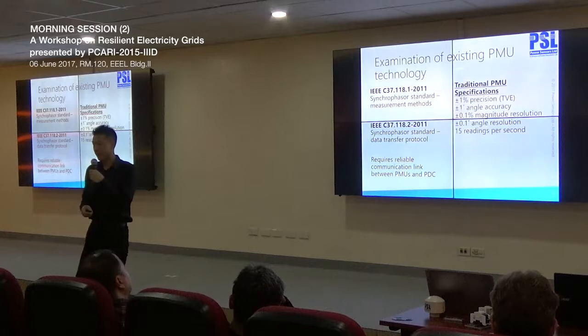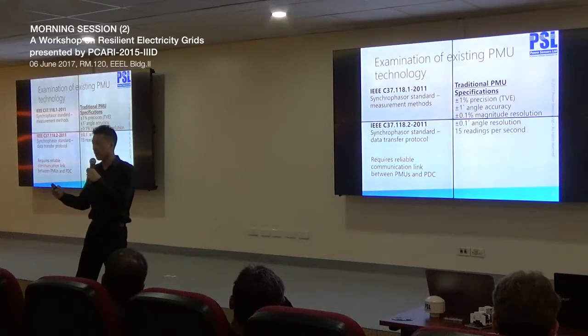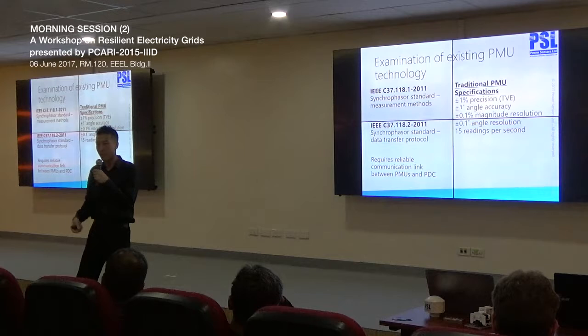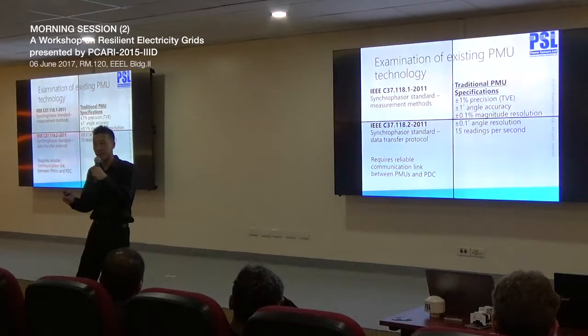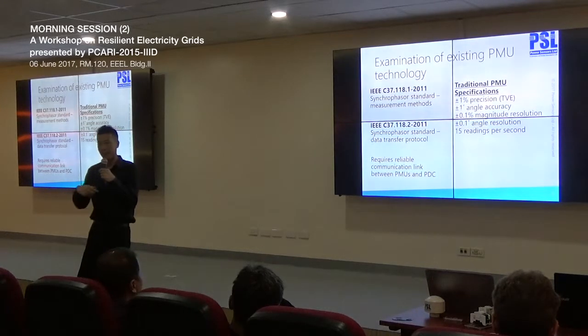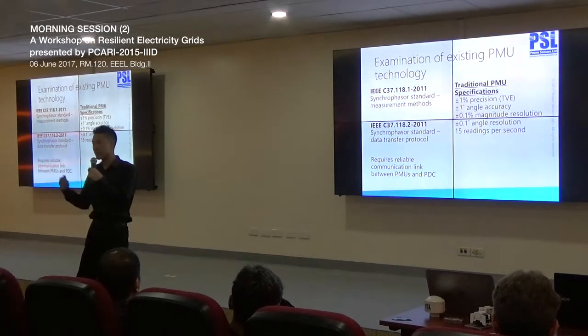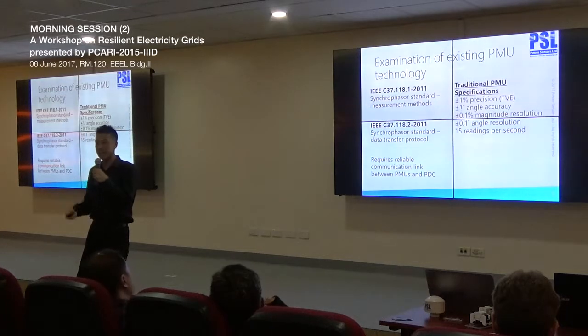The typical PMU installation requires a network of PMUs constantly streaming data to the database, which they call a PDC, or Phasor Data Concentrator. Now what happens if you drop a packet? You've just lost that data, it's gone forever. So we've identified a weakness in how the traditional PMU technology is communicating the data.